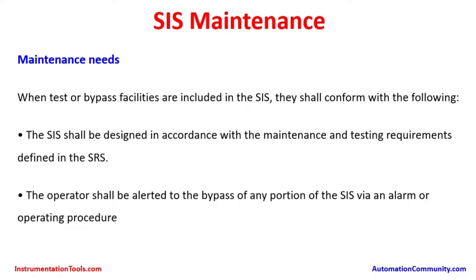Maintenance needs. When test or bypass facilities are included in the safety instrumented system, they shall conform to the following. The SIS shall be designed in accordance with the maintenance and testing requirements defined in the SRS — safety requirements specification. The operator shall be alerted to the bypass of any portion of the SIS via an alarm or operating procedure. Whenever a safety instrument system is taken out of service, the operator should be highly alerted, so that in case of any hazard happening in that area, he will have to take manual action to contain the situation.